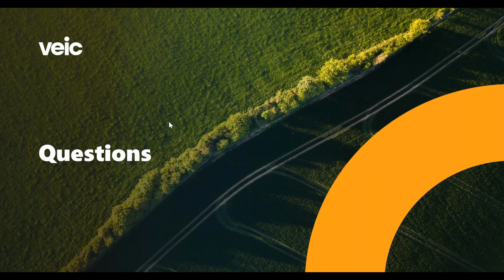That's a good question, and it totally depends. I think that's where folks in our market can provide a ton of value, because this is something customers haven't thought about previously. For customers with rooftop units, it's going to be getting creative with how we can alter the operation of those outdoor air dampers and maybe control them if they haven't been controlled before. So it's about using the equipment you have and modifying it to meet some of the requirements for 100% outdoor air, flushing the building, and disabling demand control ventilation so they never modulate down to a lower outdoor air condition. Then there's a crossover point where the building gets uncomfortable because these systems weren't designed for all this ventilation air in terms of heating and cooling coil capacities. So I think all buildings are going to be able to do better and get close with what they have.